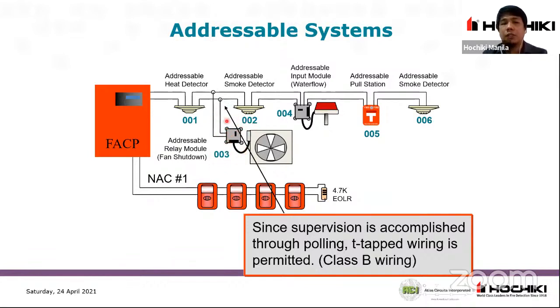So T-tapping, meron kayong derecho, tapos nagkaroon kayo ng branch dito. Hindi na issue si T-tapping since meron na tayong specific address for this. Kapag nagkaroon ng disconnection dito, makikita nyo sa panel na meron tayong open circuit trouble or disconnected device for addressable device number 3. Unlike sa conventional kasi wala tayong specific or unique code for every device. So T-tapping is allowed na for the addressable system.